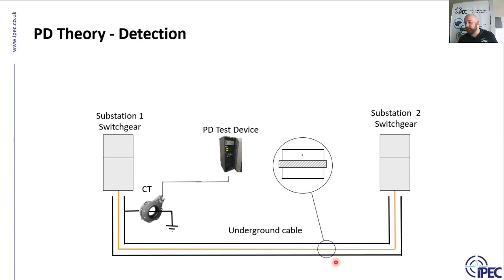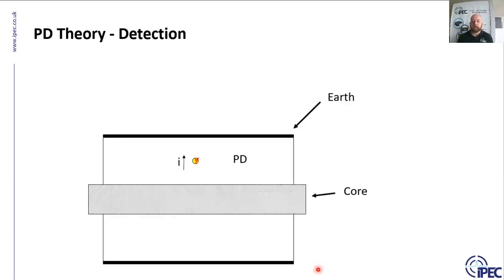Okay, so if we zoom in now to this area of the cable, let's have a look what happens. So again, this is most likely to be in a cable joint, but for simplification, I've taken the ideal solution. We've got a single core cable, high voltage cable, and the earth shield around the outside. Now, when one of these very small PDs occurs during the rising edge of the power cycle, PD is then induced on the inside of the earth sheath, and also an equal and opposite signal on the outside of the core.